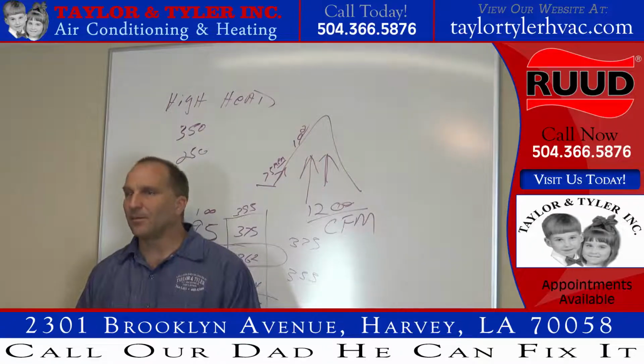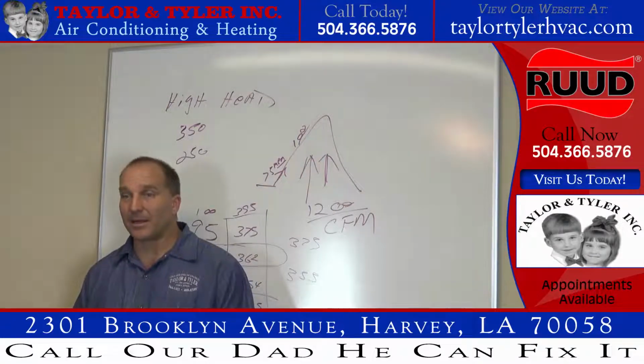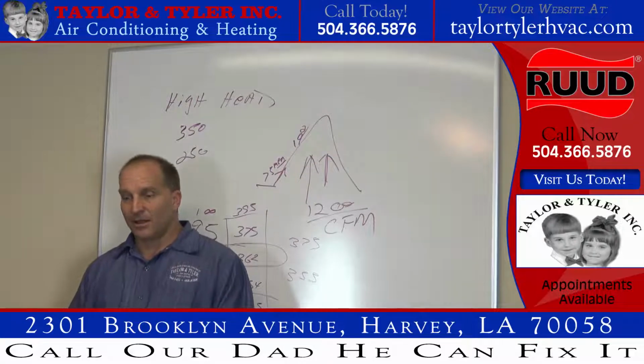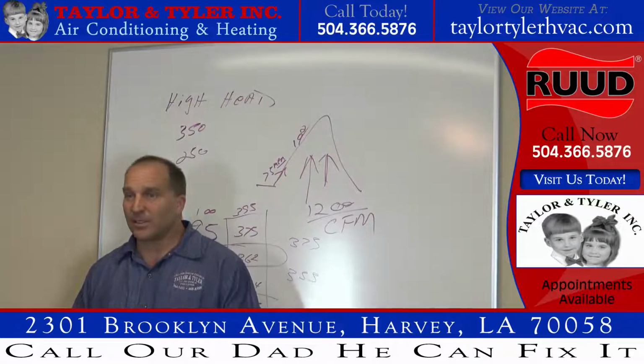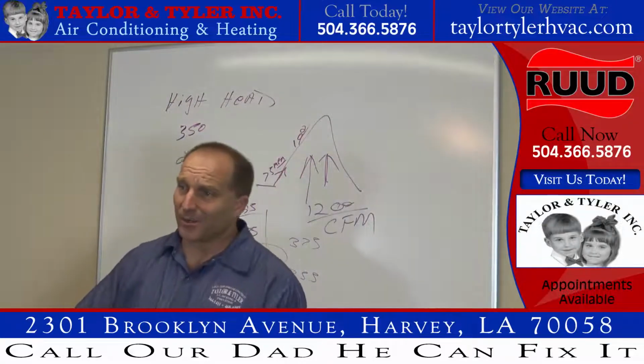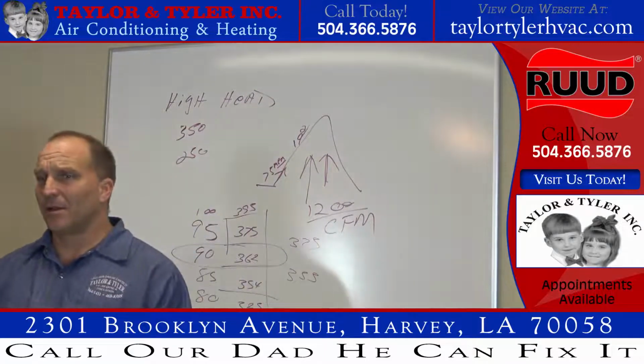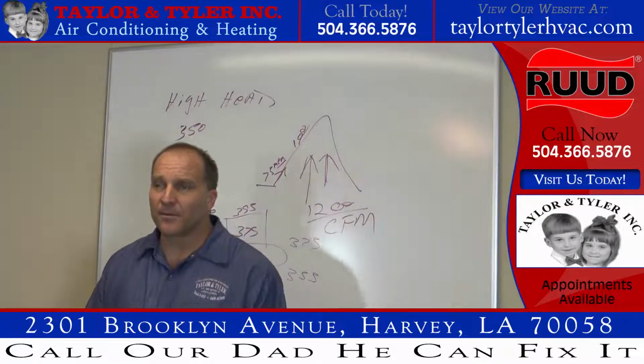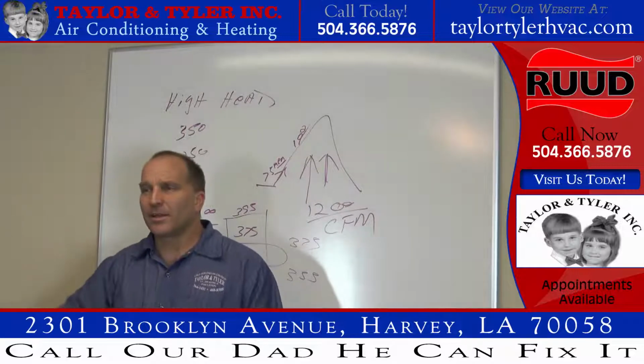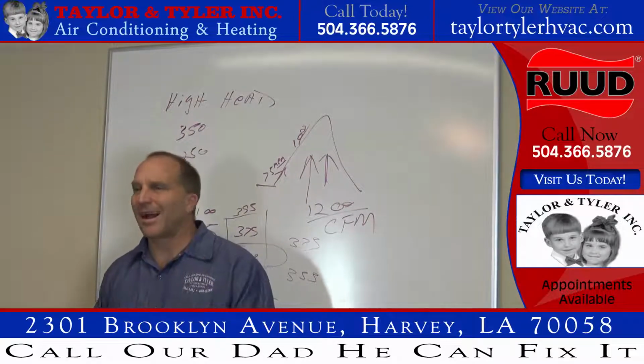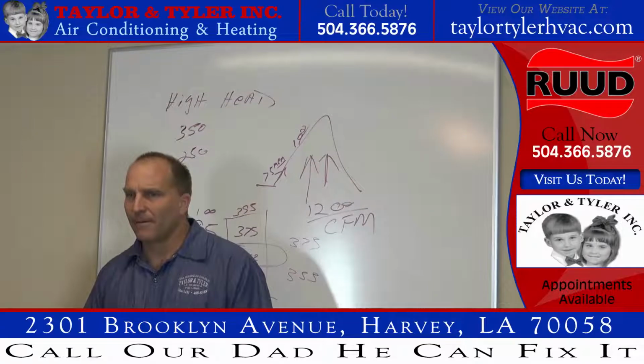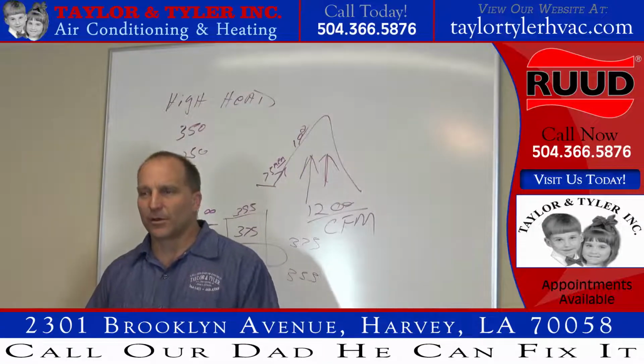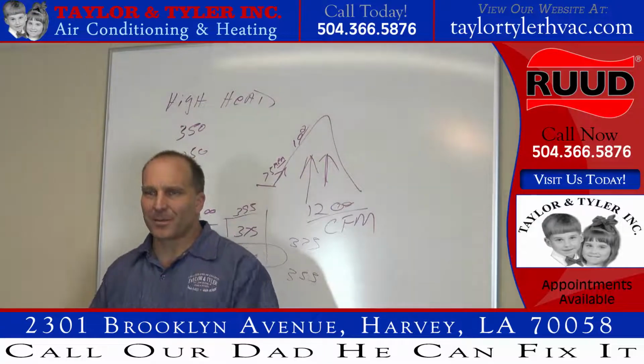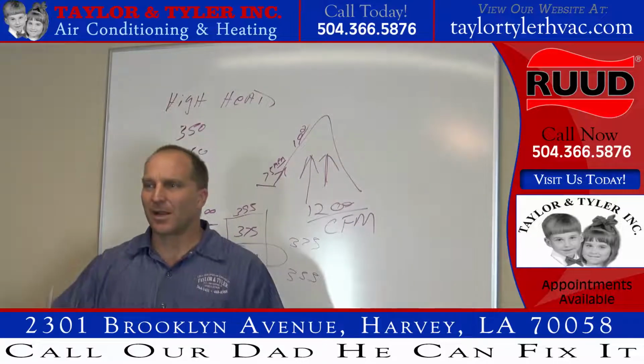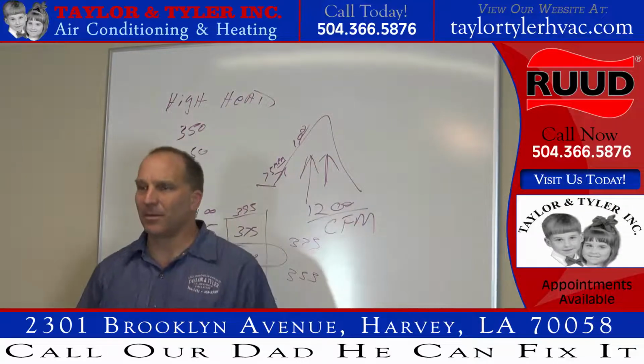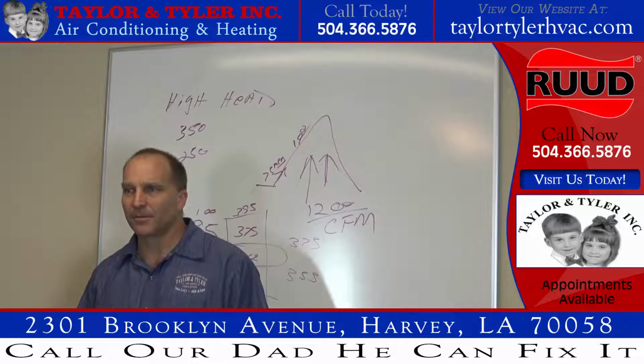I'm like, something is not right here, but I keep adding refrigerant to the system, and it's not really doing anything. It's not increasing my suction pressure hardly at all, not increasing my head pressure hardly at all, but it keeps running though. And I feel over the condenser, and I don't have real hot air coming out of my condenser either. I am adding refrigerant to the system. The heat's not coming out of the condenser. My head pressure's not coming up. My suction pressure's not coming up. What is going on here, right?